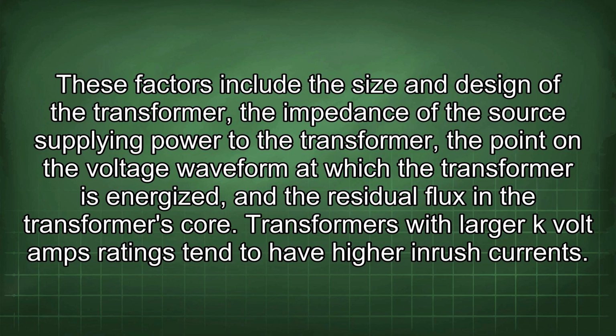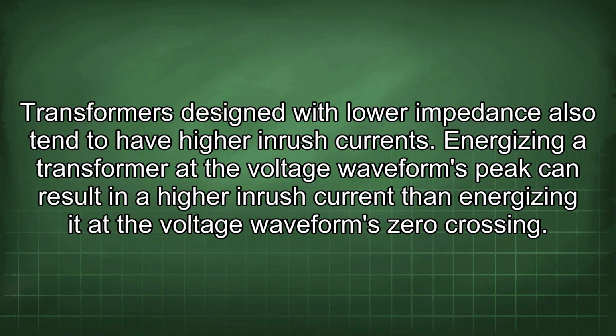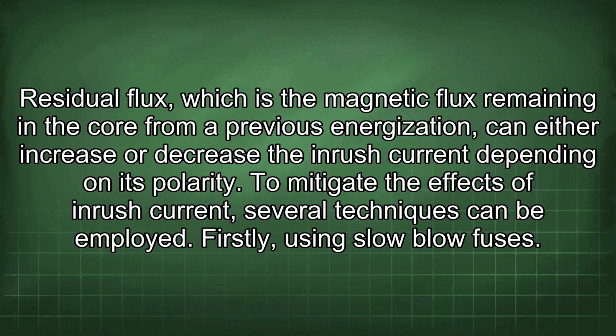Transformers with larger kVA ratings tend to have higher inrush currents. Transformers designed with lower impedance also tend to have higher inrush currents. Energizing a transformer at the voltage waveform's peak can result in a higher inrush current than energizing it at the voltage waveform zero crossing. Residual flux, which is the magnetic flux remaining in the core from a previous energization, can either increase or decrease the inrush current depending on its polarity.